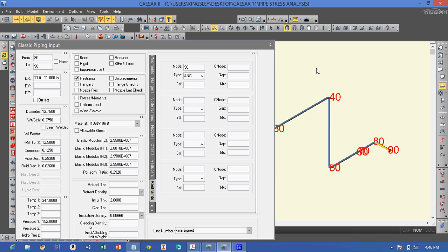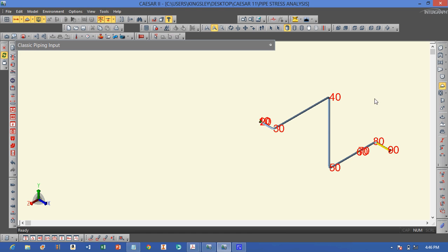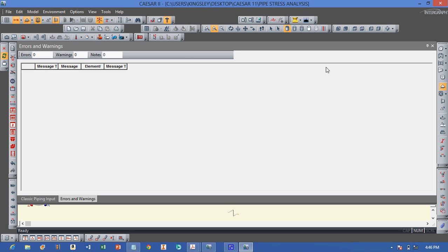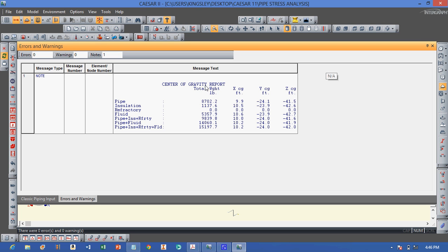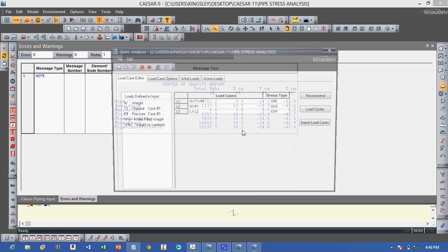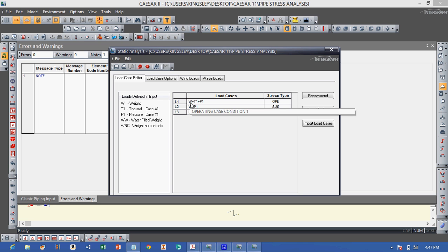This is what we are going to simulate. Let me remove the node numbers to show the pipe clearly. The next thing we do is the error check. There are no errors. We can see the dead weight of the pipe, dead weight of insulation, and dead weight of the fluid. We add these loads and then proceed to analyze — including dead weight of the pipe, insulation, fluid, thermal strain from temperature, and load from pressure.